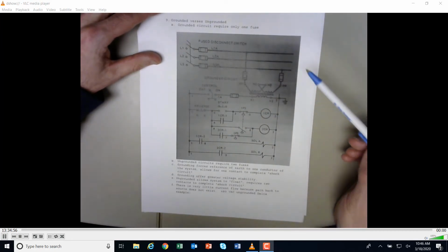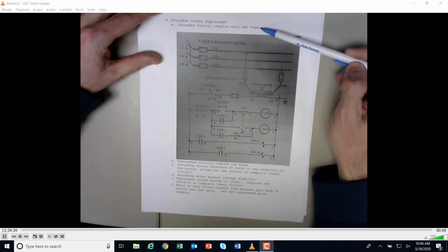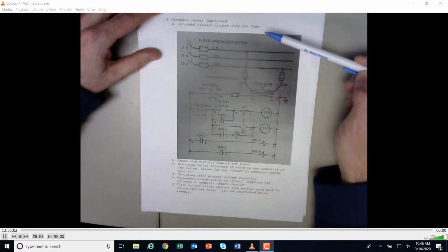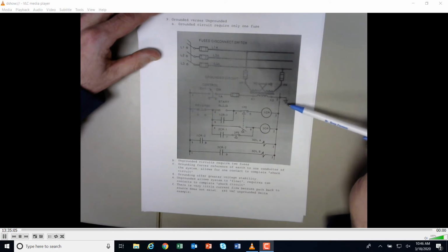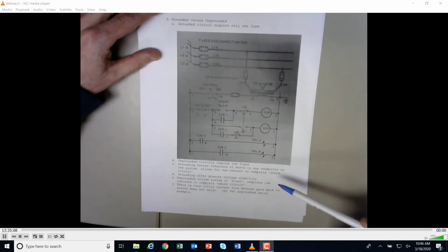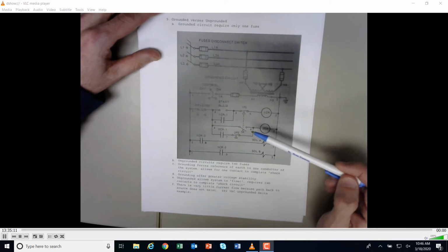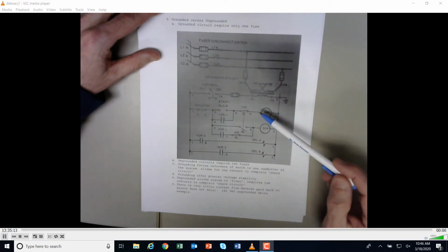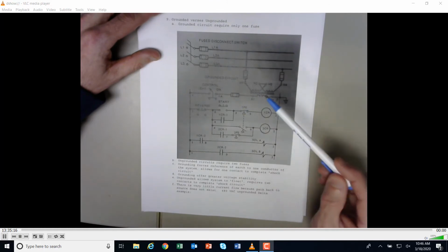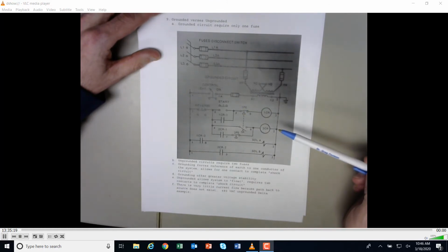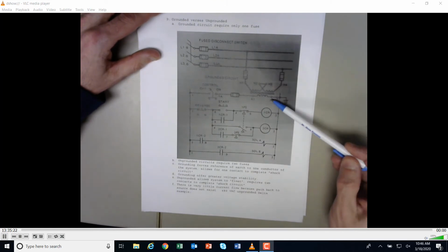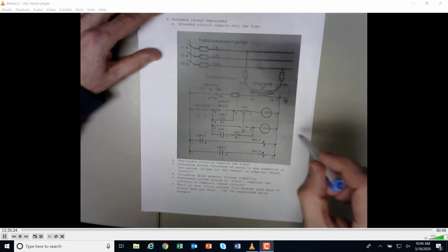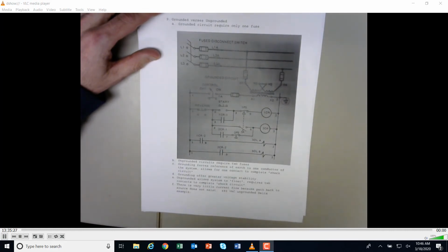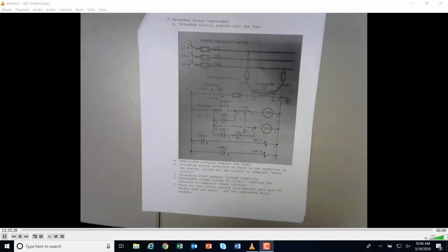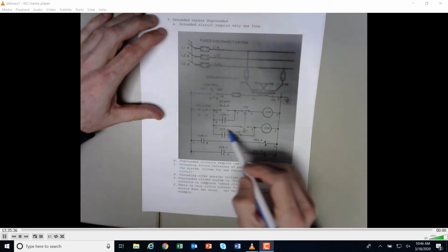So a couple of things: a grounded circuit requires only one fuse, okay? And so when you've got a problem in here, it blows the fuse, and this system is down. You have to find the problem, you have to fix the problem, and you have to get your multimeter out and fix it, or else every time you put the fuse in here, it's just automatically going to blow, okay? And that's pretty safe though, because any extra electricity is going to ground to earth, and the operator is safe, can't be electrocuted. It's safe, but the drawback is your system is down.